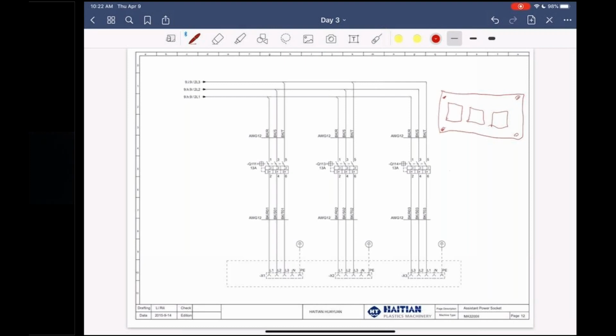So inside the box, you'll have a terminal strip. You'll have line 1, then line 2, then line 3, and then you'll have your ground. So you pick one wire from line 1, 2, and 3, and then your ground, and you can have a 3-phase circuit. But again, keep in mind that's not included in the full load amperage of the machine. So if your machine full load amperage is 40 amps, you have to add another 40. So it'd be actually an 80 amp full load on the machine. Yeah, so your drop has to be adequate for that. Your drop, your wire size, everything.